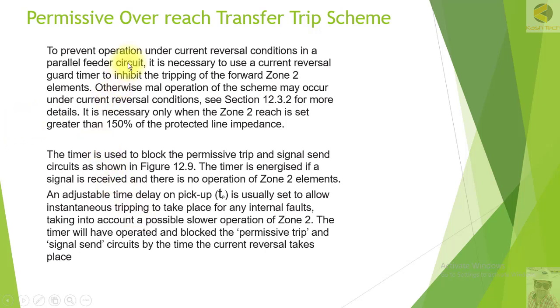To prevent operation under current reversal conditions in a parallel feeder circuit, it is necessary to use a current reversal guard timer to inhibit the tripping of the forward zone 2 element. Otherwise, maloperation of the scheme may occur under current reversal conditions. This is necessary only when zone 2 reach is set greater than 150% of the protected line impedance.